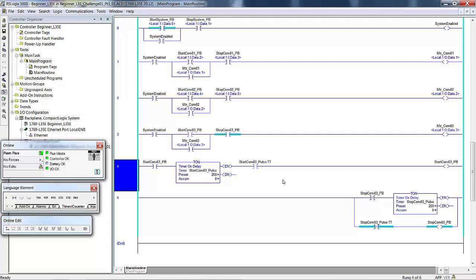The system start was already on, and that is a toggle switch or push button. Now what we're missing here is we need input 1 on, because that's the stop push button. And remember that the stop buttons are normally closed, so we need to turn on 3 and 5. We want all the stop buttons to be on right now because we're simulating normally closed, so those bits would be on in memory and those instructions would be true.